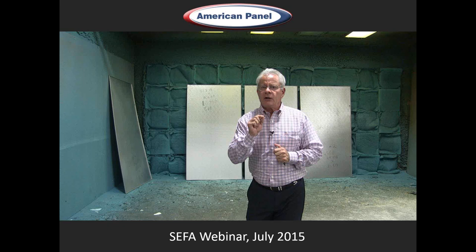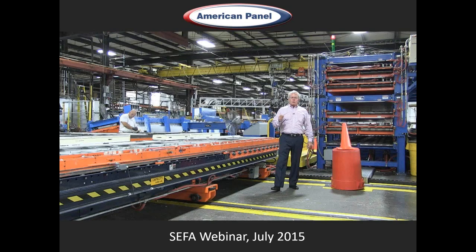Now we've got our perfectly measured, notched, grooved, punched, treated metal — what happens to it next? It goes into a fixture, and there are many fixtures that make up the manufacturing process here at American Panel. Behind me is our newest addition — a multi-million dollar heated and cooled stack press. There are four openings that have a bed at the bottom and a platen, which is the portion of the fixture that squeezes down on the panel to make sure it is exactly 4.00 inches thick — or 5.00 inches thick — ensuring that when we inject the expanded polyurethane, it doesn't get out of tolerance. Immediately to my right is one of the shuttles that will go into the fixture — it's pumped, and the foam expands as part of the integral panel.